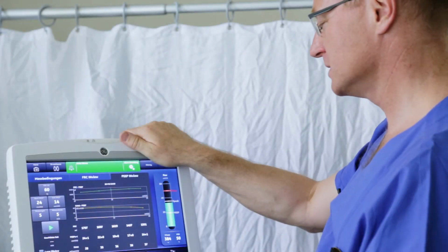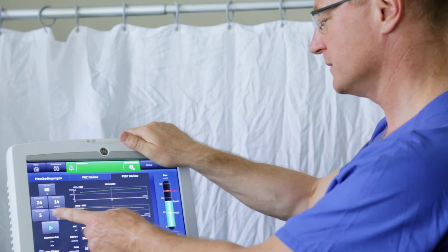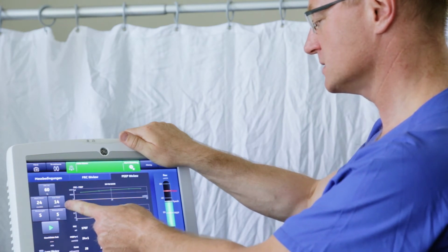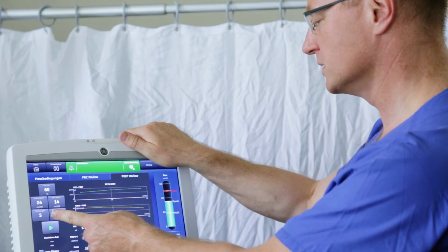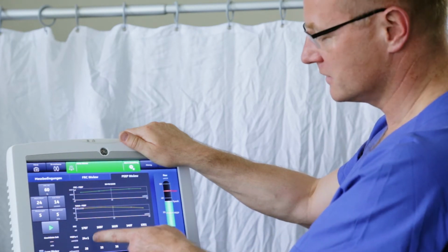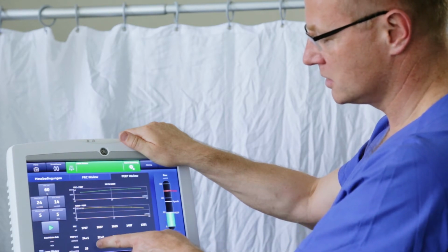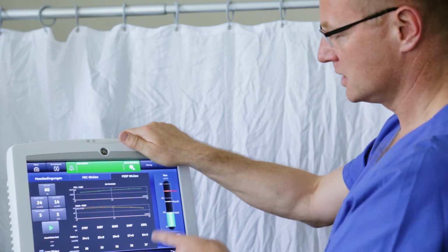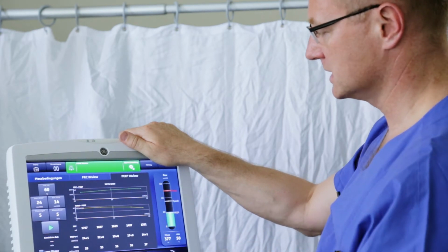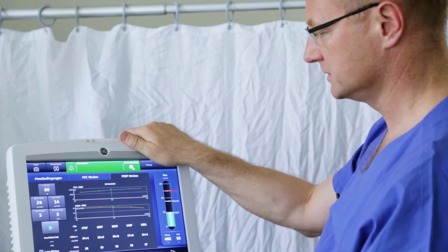The PEEP in-view measurement is now finished. Here we have our PEEP value with the start at 24, our end PEEP at 14, 5 measurements over a period of 5 minutes per level, and over there we can read the individual values for FRC, PEEP, and static compliance. At the top we see everything displayed again in the form of a graph. We have now seen how the bedside measurement procedure is performed. All that is missing now is an analysis of the results, which we will now perform together.